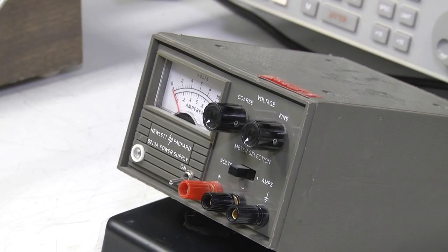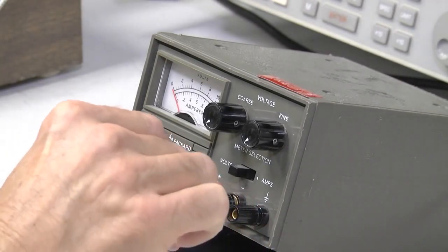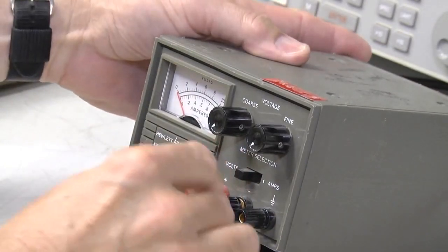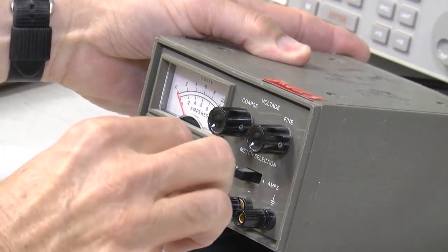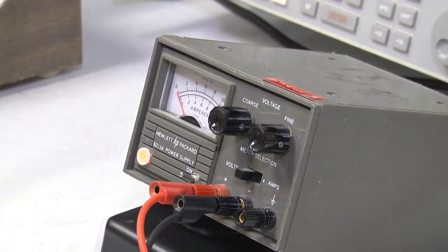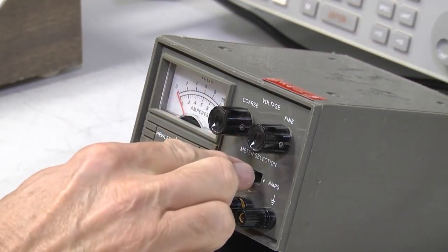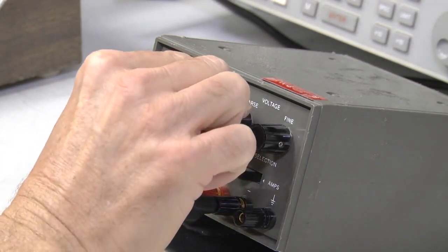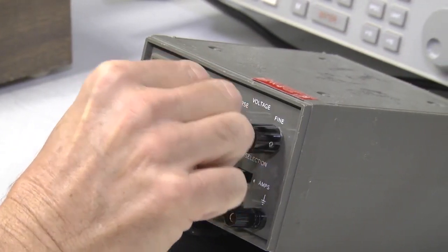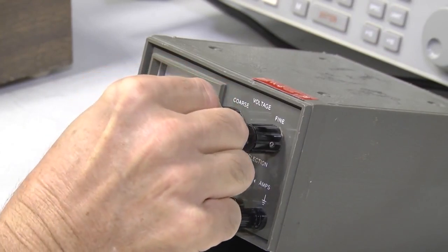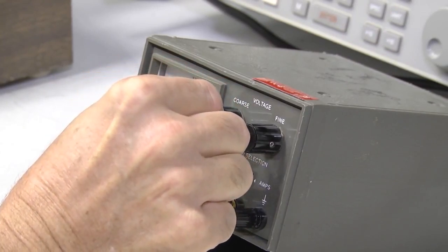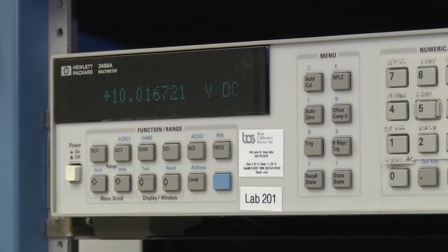The first thing that we're going to do is check the meter for accuracy on DC volts. So we'll go ahead and connect the digital multimeter to the power supply. We'll turn the power supply on with the meter selected in the volts position. We'll increase the output to full scale, which on this particular unit is 10 volts. Bring it up to 10 volts, like that. Looking at the indication on the HP 3458A digital multimeter, we see that it indicates 10.01 volts. That's within the specification of the HP power supply.